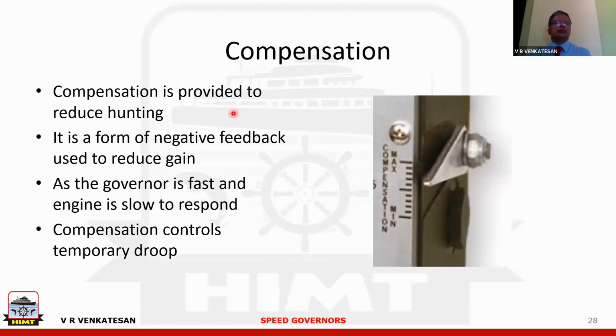Right. The compensation, what is the meaning of compensation? It is to make the governor achieve the speed faster and in stable condition, not to overshoot or undershoot. Compensation is provided to reduce hunting. Why does hunting take place in a governor system?